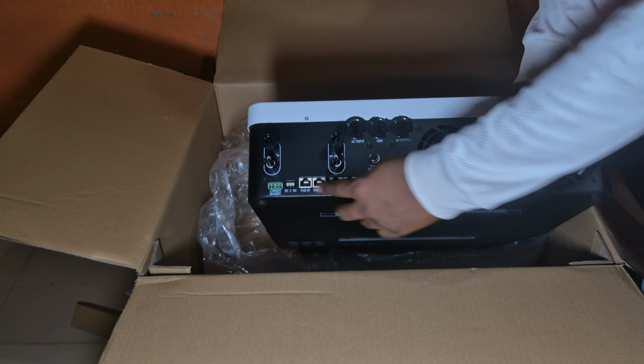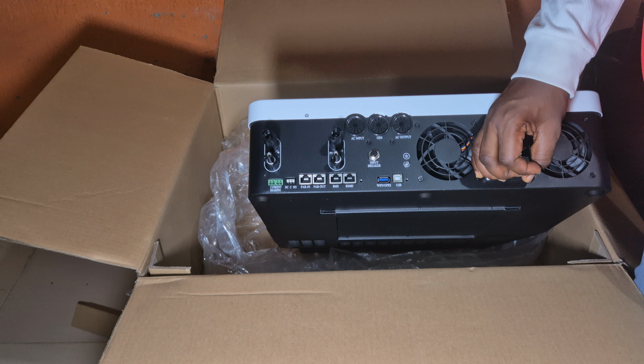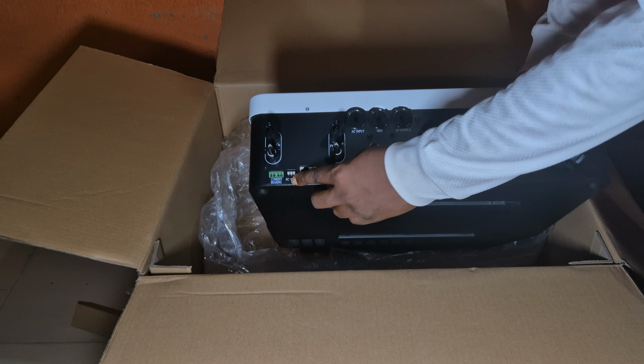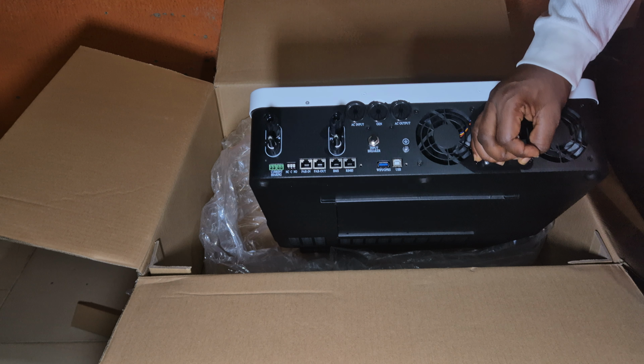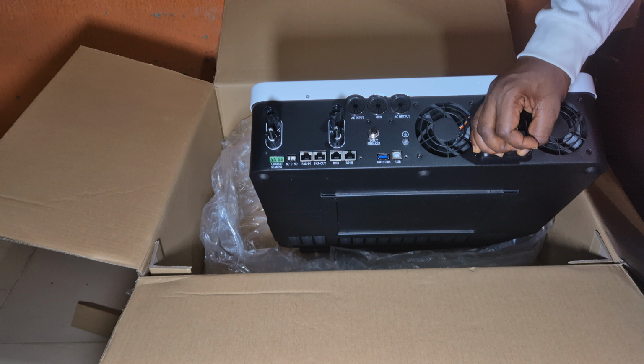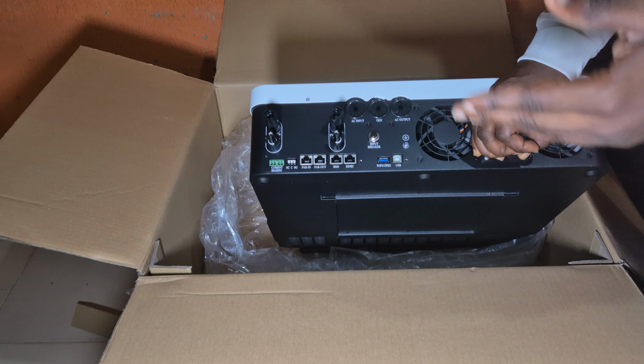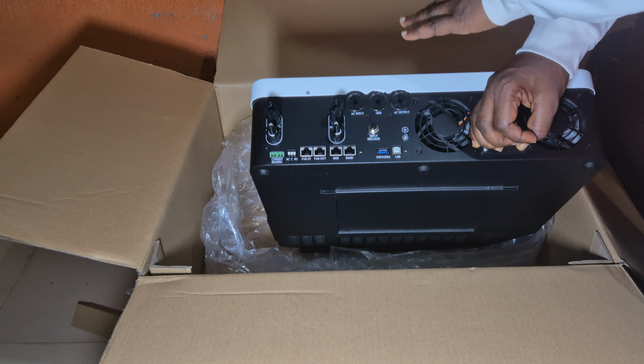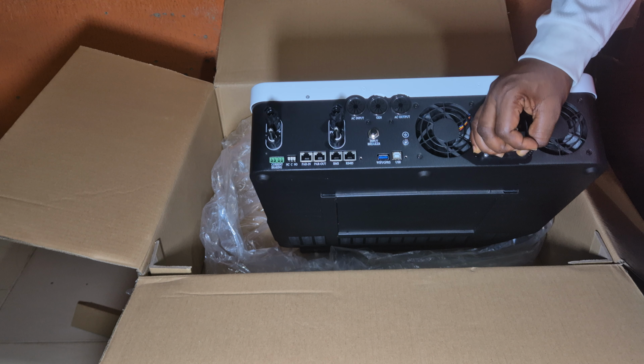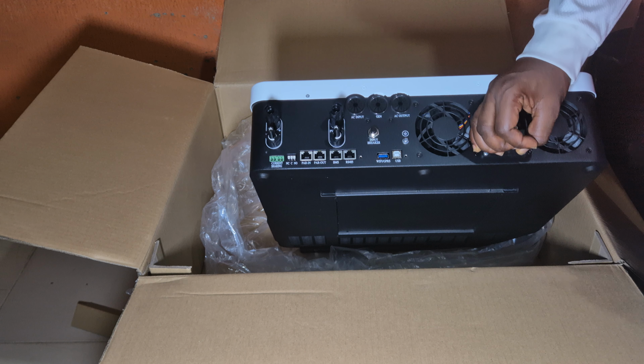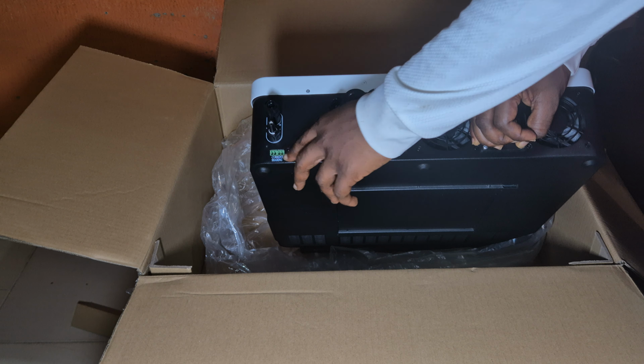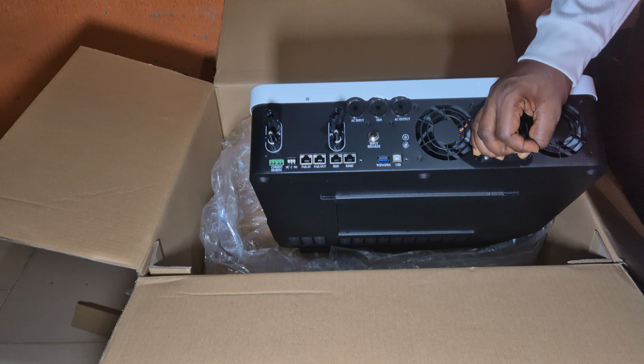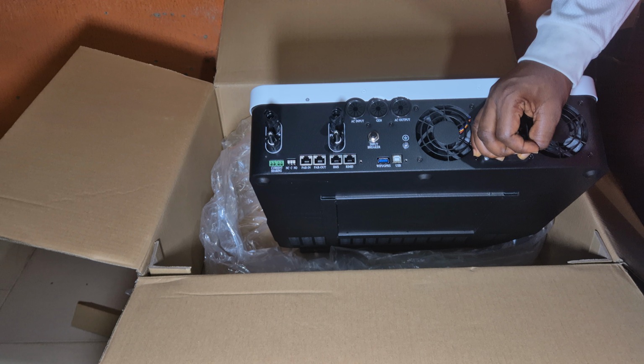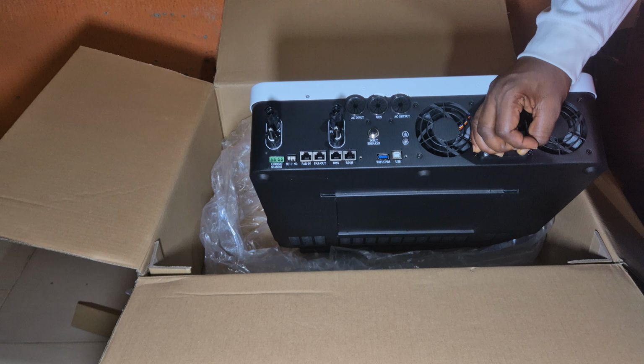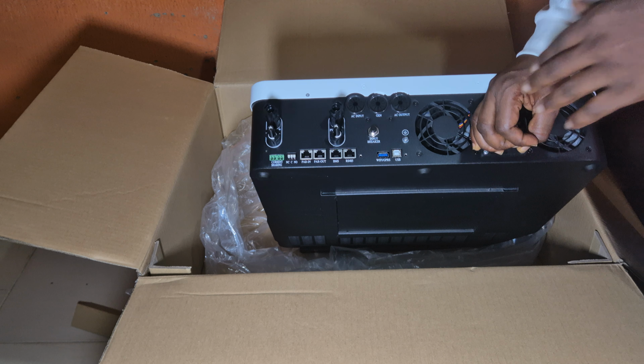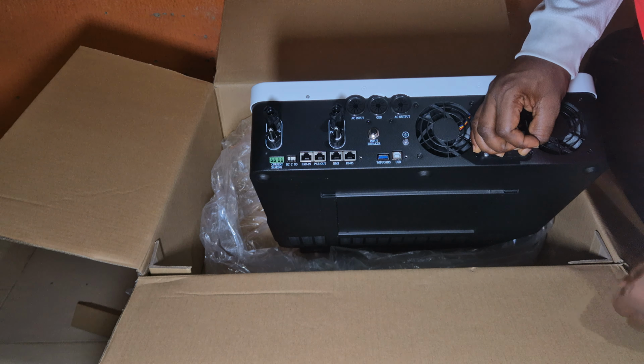Below here we have some connection points. The first one you see there is called current sharing. That is where you connect the communication cable I showed you earlier. In case you want to make this one master, and another inverter like this a slave, this is where you connect those communication cables. The inverters speak to themselves, they know who is master, who is slave, and how to balance their current sharing.